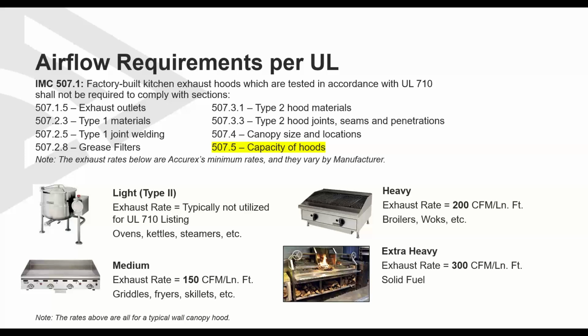Since our hoods are UL 710 listed, we actually have lower exhaust rates because per IMC 507.1, factory-built kitchen exhaust hoods, which are tested in accordance to UL 710, shall not be required to comply with sections, and there's a variety of sections here, but the one I highlighted is capacity of hoods. So you can see, looking at the heavy-duty appliance here, our exhaust rate that we tested to is actually 200 CFM per lineal foot.